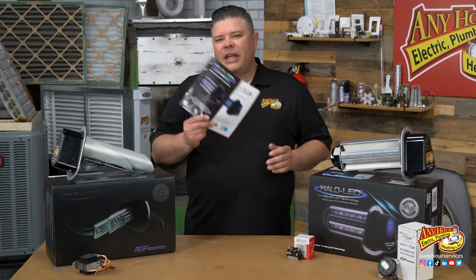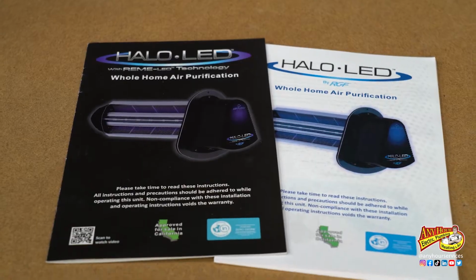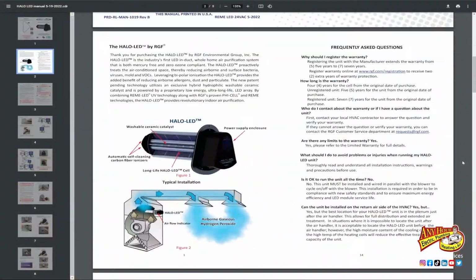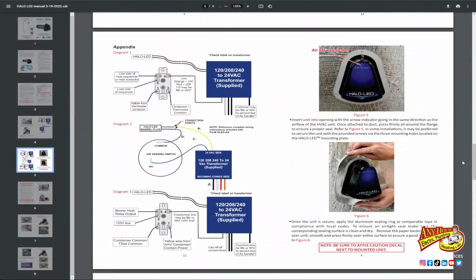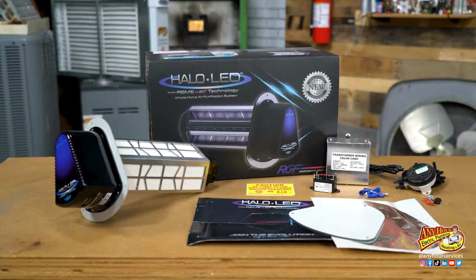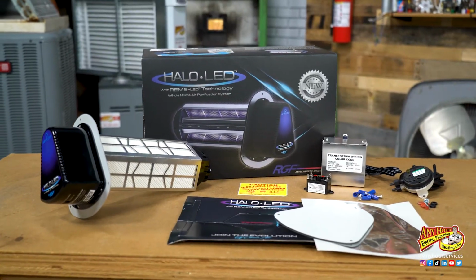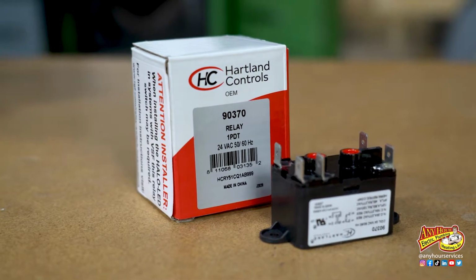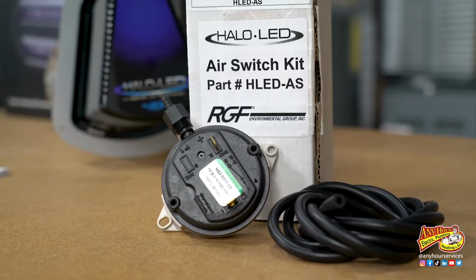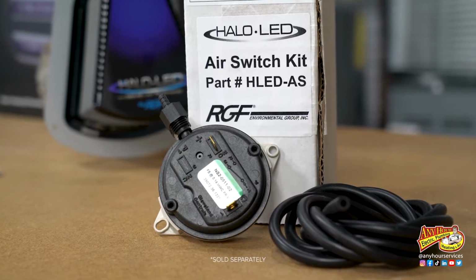Now, RGF updated their installation manual to include more options and details about wiring up different furnaces. So make sure you're using the most up-to-date version. Now, out of the box, the Halo LED comes with a relay that's good for most installs. However, the air switch is simpler and works on any install, but it doesn't come in the box, so you'll have to get that separately.